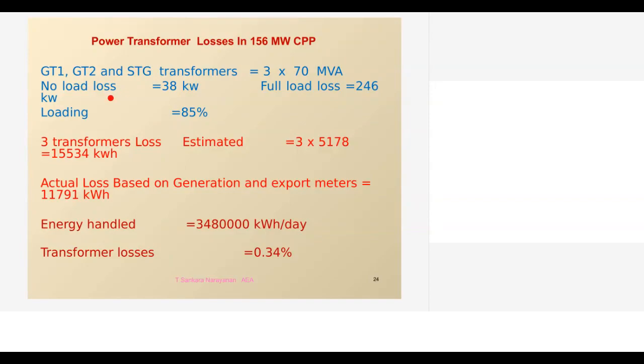So we did one day of monitoring for all 3 transformers, then estimated the transformer loss. All 3 transformers put together, load loss plus no load loss, the estimated loss is 15,500 units. Luckily, because this is a generating station, each generator has a generation meter, and at the outlet where they export power, there is a feeder meter. We took all the generation meters and the export meter. The difference is only 11,800 units. Calculated was 15,000. Actual loss was 11,000.